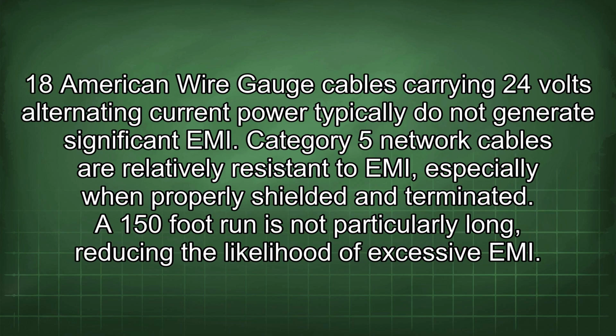18 American wire gauge cables carrying 24 volts alternating current power typically do not generate significant EMI. Category 5 network cables are relatively resistant to EMI, especially when properly shielded and terminated. A 150-foot run is not particularly long, reducing the likelihood of excessive EMI.